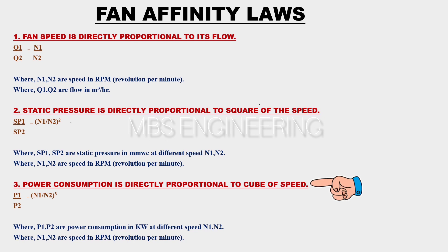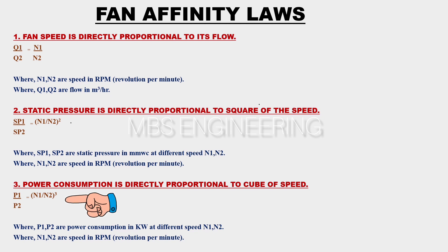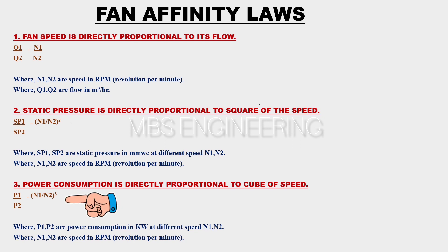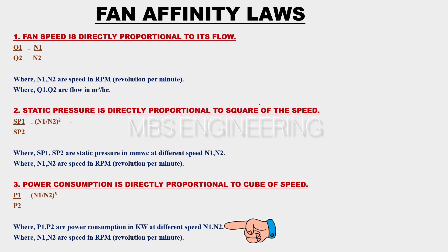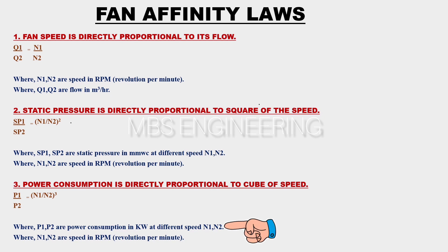Power consumption is directly proportional to the cube of speed. The power consumption P1 divided by P2 is directly proportional to the cube of speed N1 divided by N2. Where P1 and P2 are power consumption in kilowatts at different speeds N1 and N2, and N1 and N2 are speeds in RPM (revolutions per minute).